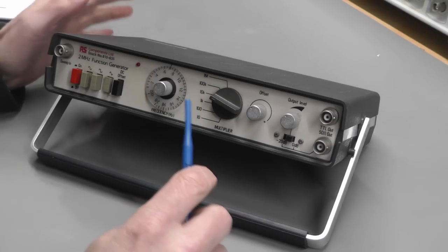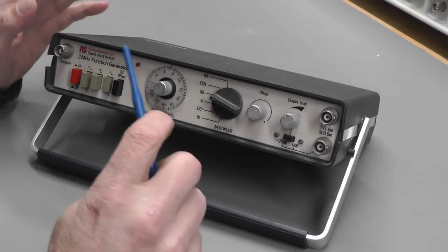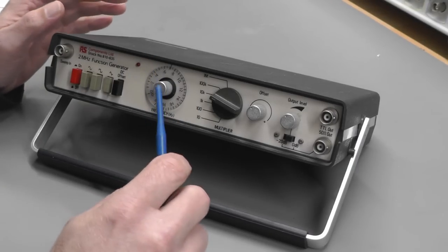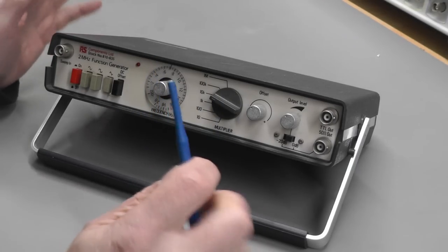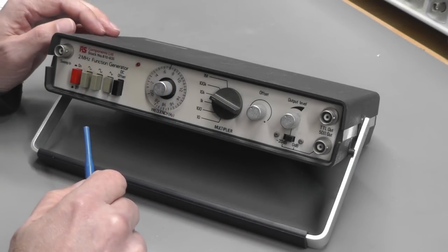Before I actually put power into it, let's open it up. Let's take a quick look inside and make sure there's nothing obvious or dangerous before we put power into it.